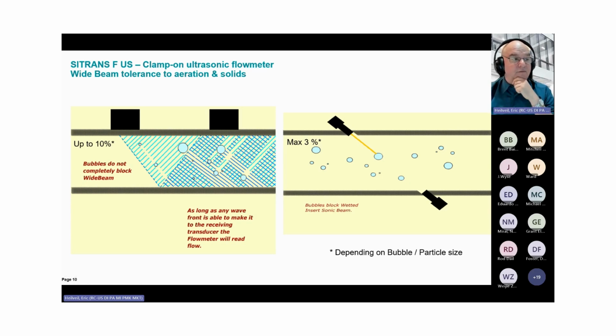There's a lot of other stuff that I'm leaving out, but the fundamental part is that if there are particulate matter or air bubbles in this type of installation, you have the opportunity to overcome the noise or the interference that the particulates or the gas bubbles can create. Because you can imagine if there was a piece of rust or something, this signal would bounce back immediately. But with a very broad footprint in direct reflect mode on a pipe, you get a chance to have a lot of information and overcome a lot of noise resistance.